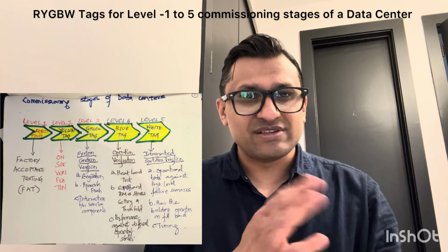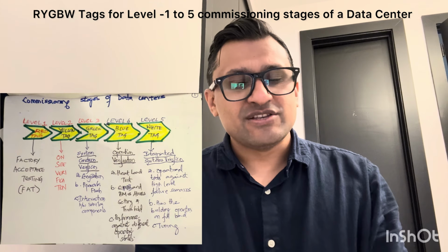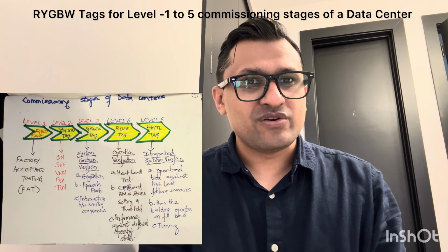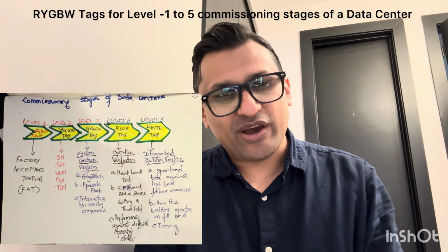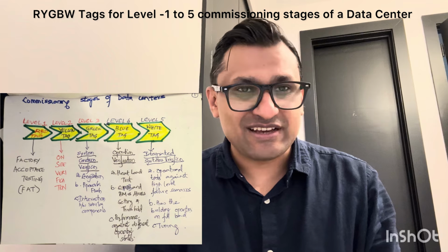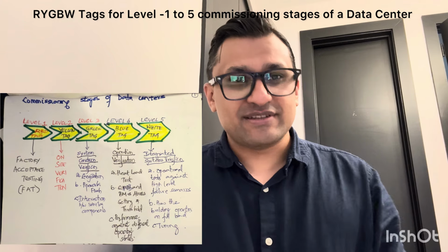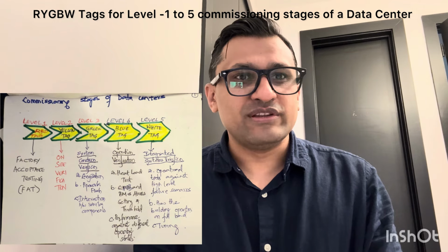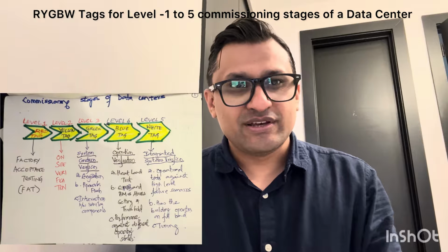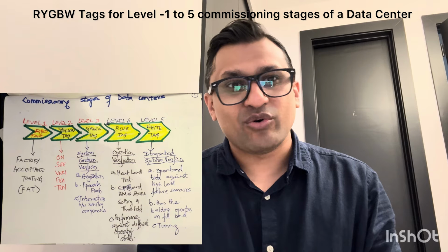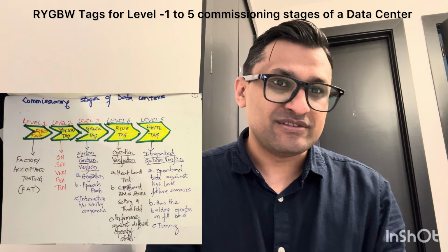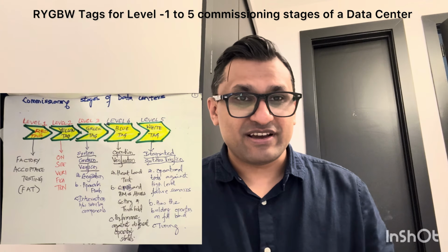And remember this, ROY G BIV. So it's red, yellow, green, blue, and white tag. So level 1 is a red tag, and it's factory acceptance testing. Where you have all the systems which are being used in the data center, before they arrive on site, they will be tested on the factory premises. So that's the factory acceptance testing.